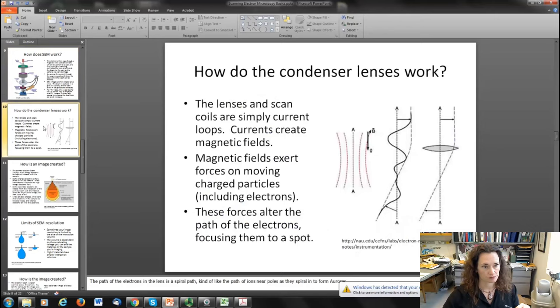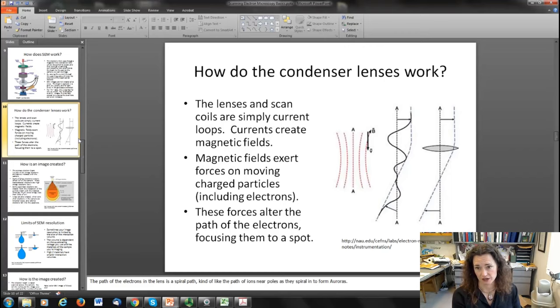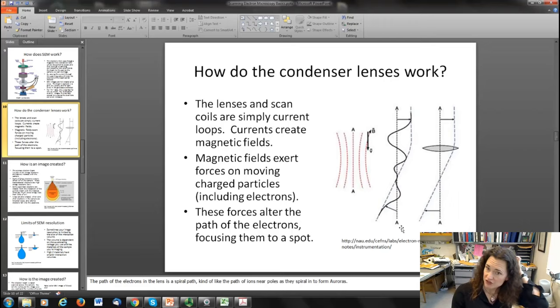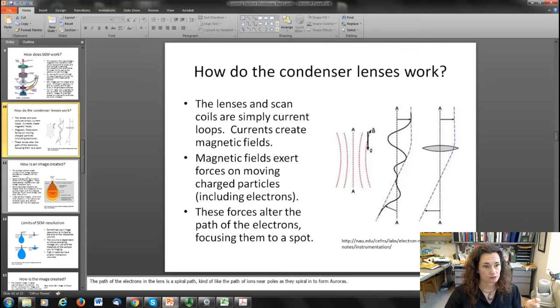How do the condenser lenses work? They're current loops. The current loops create magnetic fields, and the magnetic fields exert forces on the moving charged particles — the electrons — altering their path in a helical mode that focuses them down to a spot, and then the electrons go back out. They usually pass through a couple of these condenser lenses in a typical SEM.